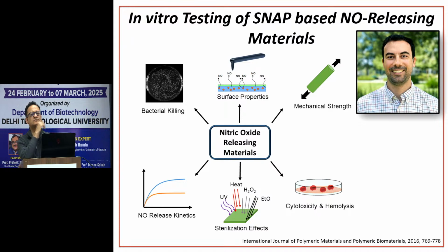If the catheter has a shelf life, I mean, if it is releasing nitric oxide and suppose, as you said, the time is 20 days, and it is packed and kept like that, if I've not used it, then also the NO will deplete. No. So 20 days is testing at 37 degrees in buffer.